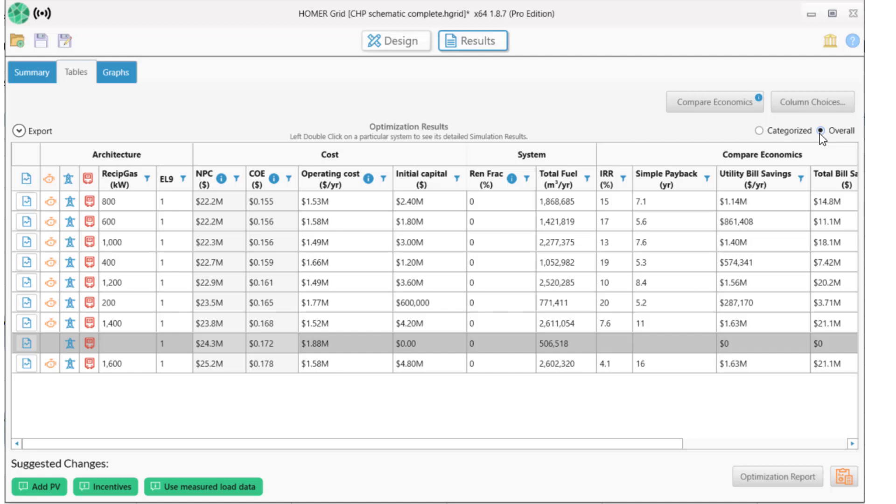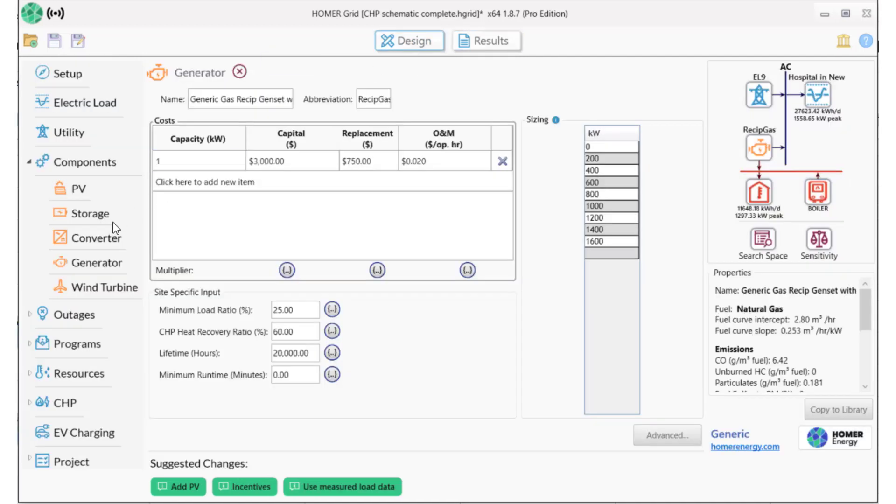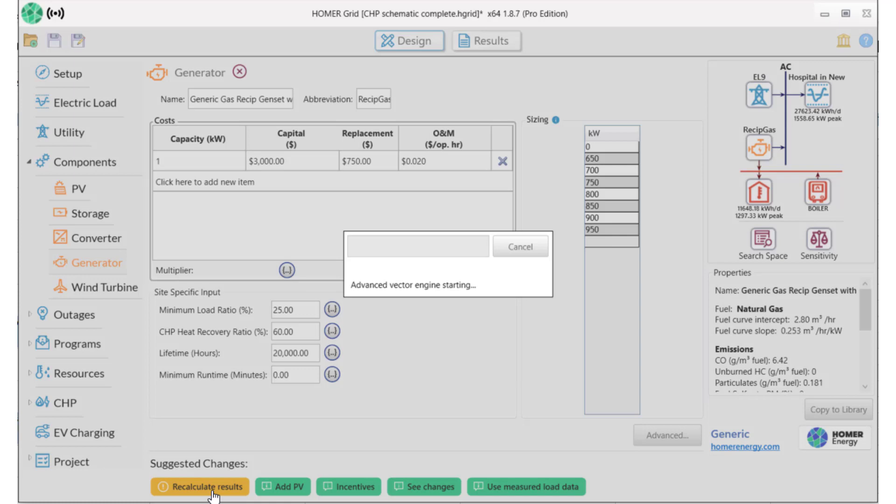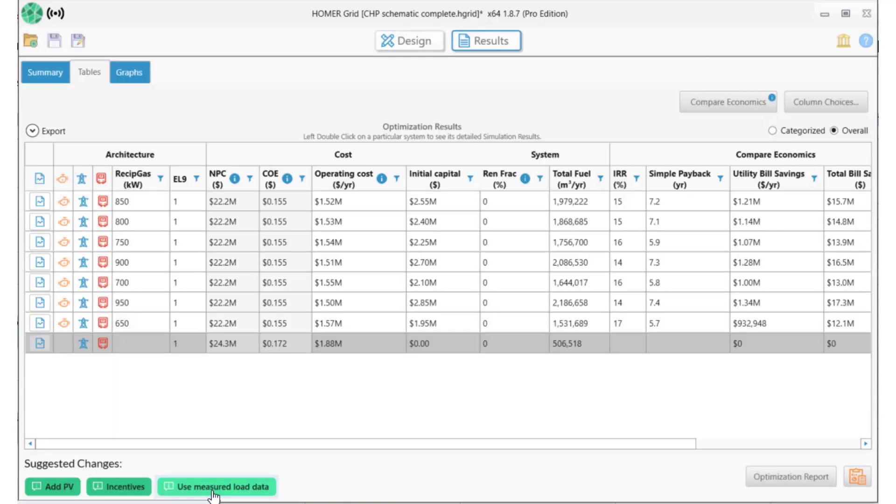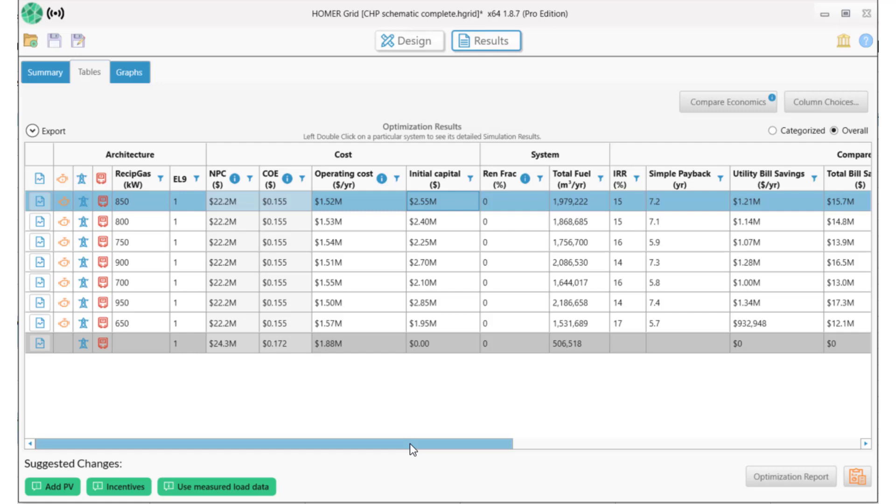We click on Design Generator. Since the winning system was 800 kilowatts, which outperformed both 600 and 1000, we'll explore sizes between 650 and 950 kilowatts in 50 kilowatt increments, and then select Recalculate Results. The winning system is now 850 kilowatts, so now we're probably very close to the right sizing. The internal rate of return and return on investment are similar to before, but the overall savings has increased.